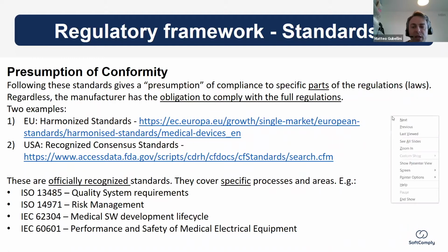There are two links here that you can use to give a look at what these standards are. They're called harmonized standards in Europe and recognized consensus standards in the US. And the lists are pretty long, especially the one in the US, as I said. So it's not mandatory that you comply to them, but probably you should, if you could, because it's a way to show that you are compliant. So you don't have to figure out a way to comply yourself. You don't need to create a new method. You just use the standard, for example.